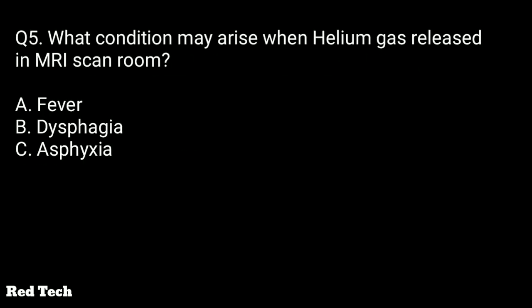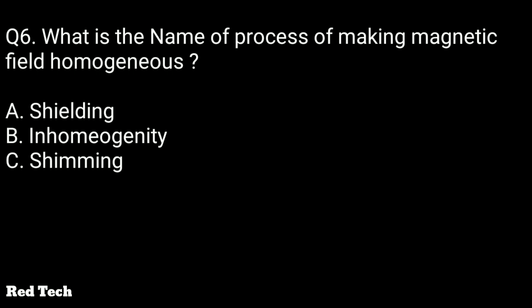Question number five: what condition may arise when helium gas is released in an MRI scan room? The options are fever, dysphagia, or asphyxia. The right answer is asphyxia. This mainly occurs in an emergency or accidentally when an object gets stuck in the MRI. Helium is released into the room, replacing the oxygen level, which causes asphyxia for anyone in the room.